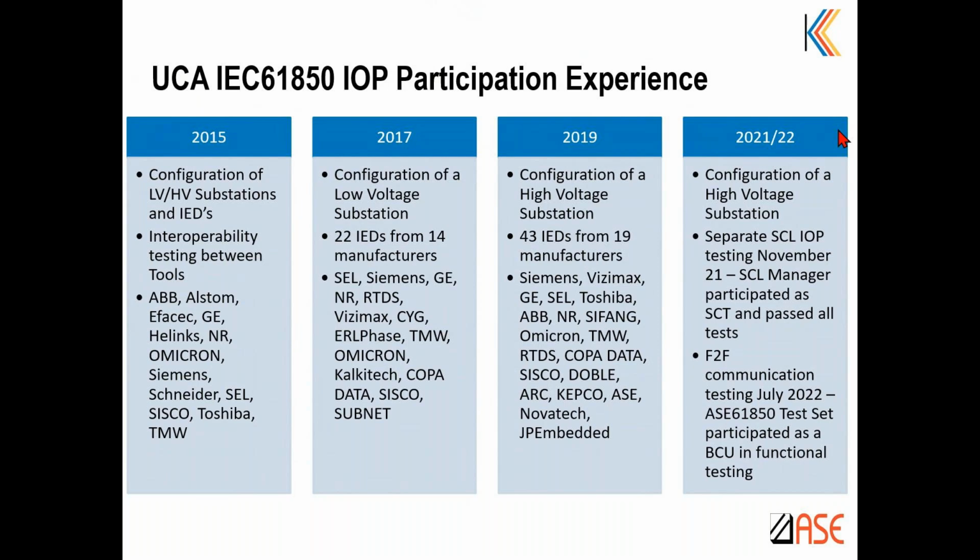In the initial stages, we used to split the entire IOP into 2 areas, like high voltage and low voltage areas. And SCL Manager used to configure one of those substations to import all the configurations, ICD files into the project and create the signal mapping and do the system engineering. We have interoperated our SCT tool with almost all the vendors in the industry. You can see the bigger list here.